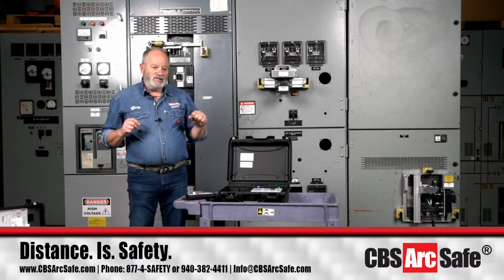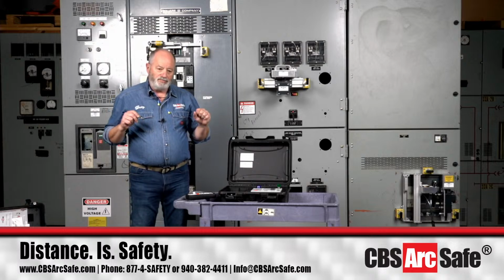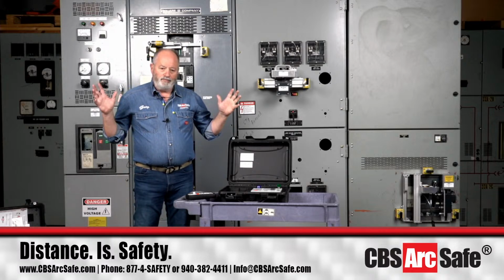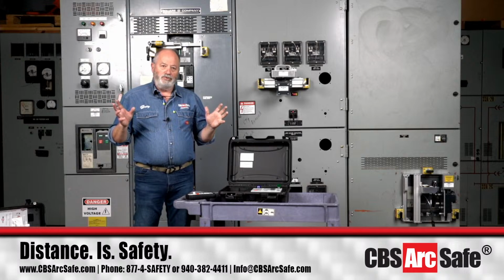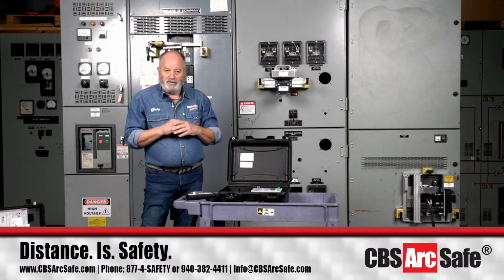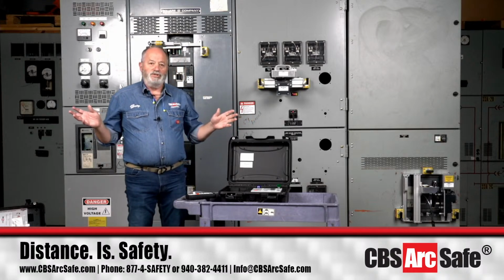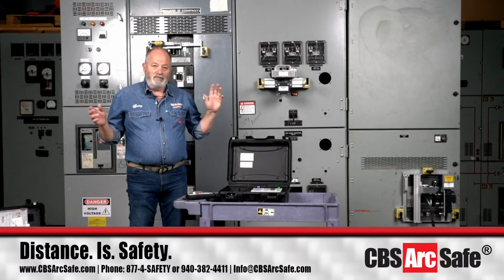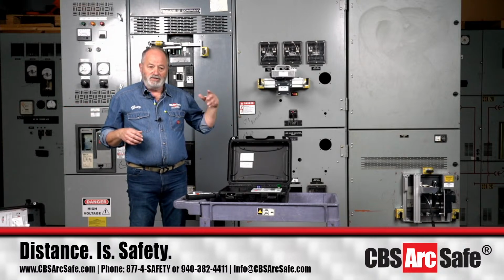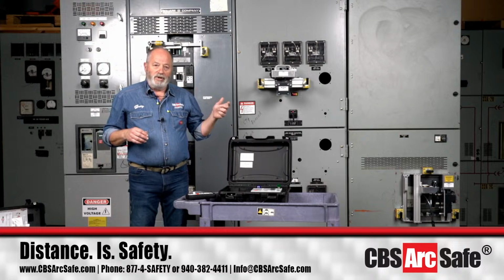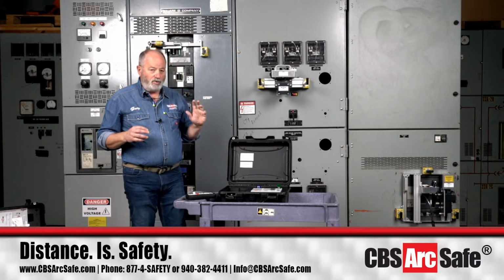The number of times I've seen rooms like this -- it's because you're working to design and put all this stuff into a single room, and you can have like 20 plus rooms in a data center that's big, where you've got main-tie-main setups like this. You've got to be able to rack these breakers, and you want to be able to also switch them.